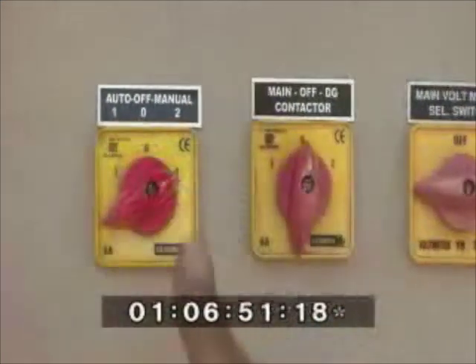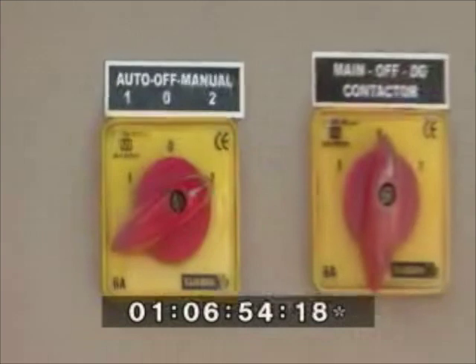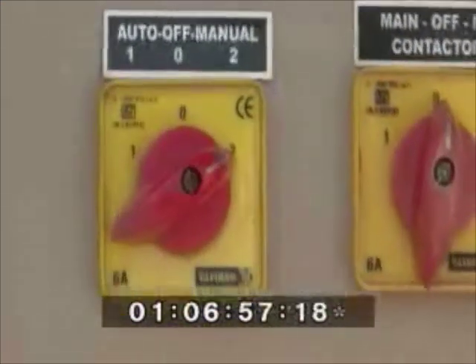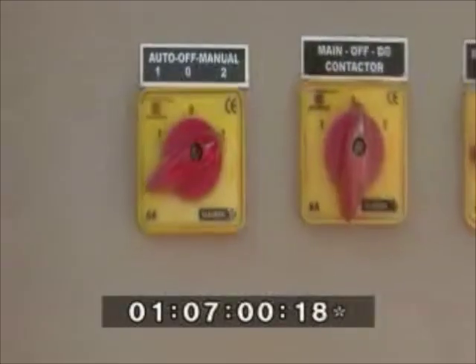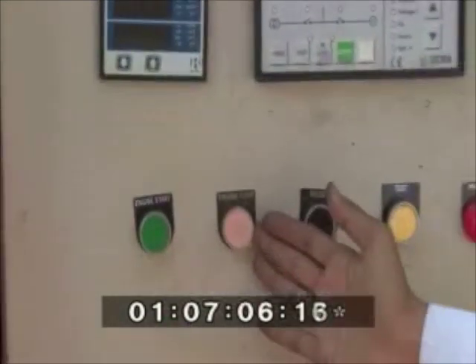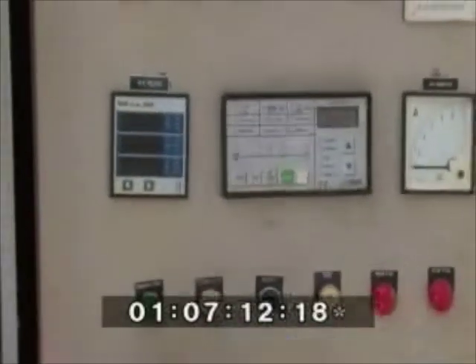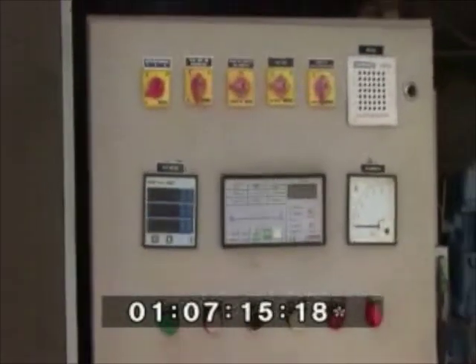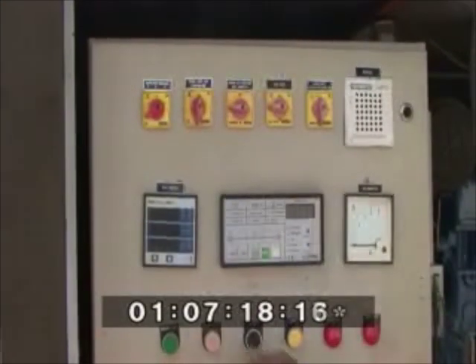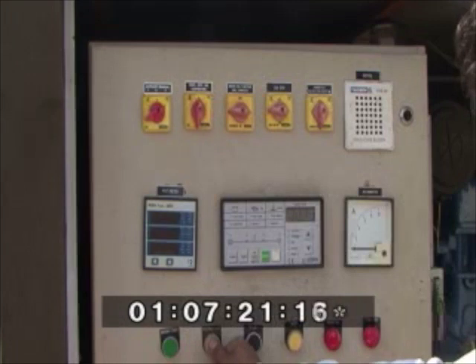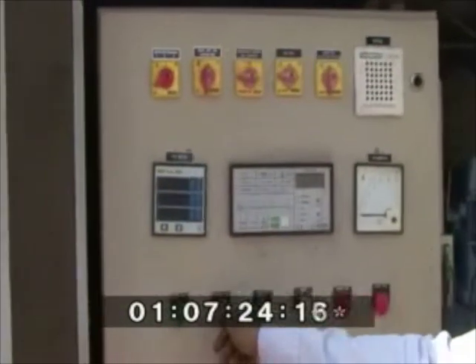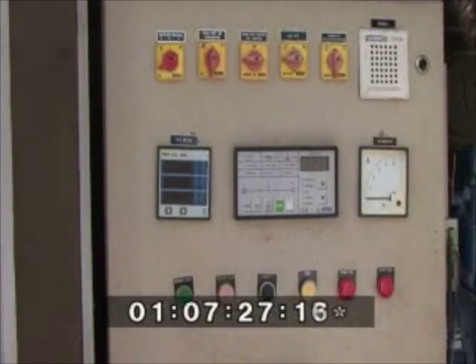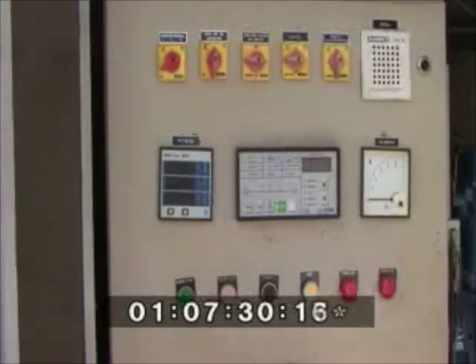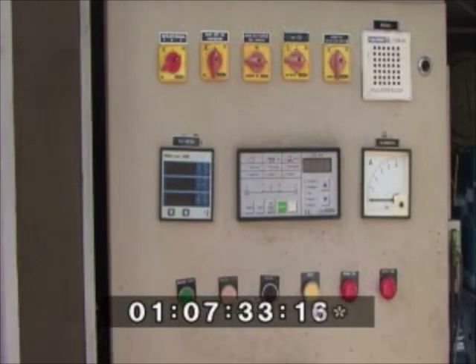At the bottom of the AMF door, we have a few push button switches. The green one is to start the DG, and the red one beside it is to stop the DG. We will first press the green button. You can hear the DG starting, so it is working in the manual mode. We will now press the red button. You can hear that it has stopped working. So the DG is working perfectly in the manual mode.